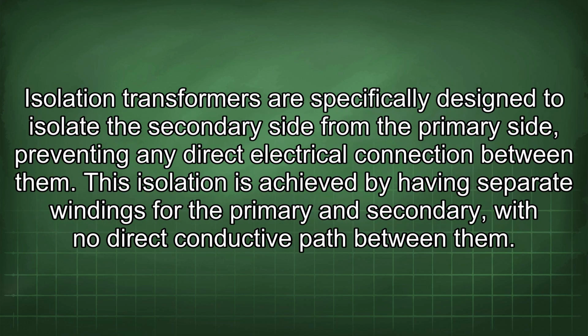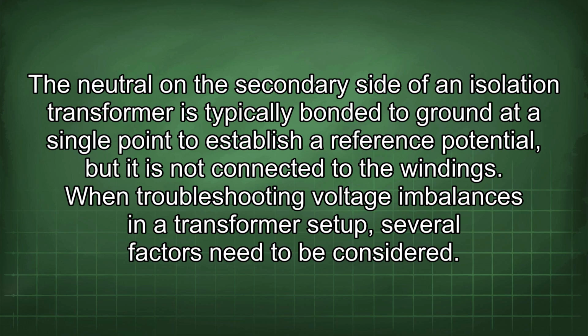Isolation transformers are specifically designed to isolate the secondary side from the primary side, preventing any direct electrical connection between them. This isolation is achieved by having separate windings for the primary and secondary with no direct conductive path between them. The neutral on the secondary side of an isolation transformer is typically bonded to ground at a single point to establish a reference potential, but it is not connected to the windings. When troubleshooting voltage imbalances in a transformer setup, several factors need to be considered.